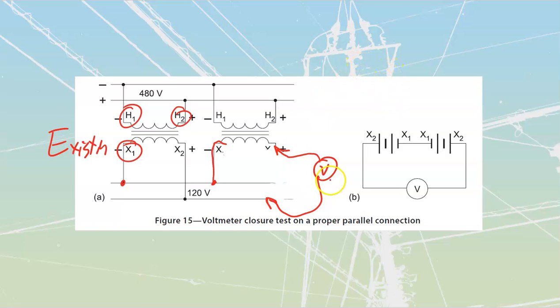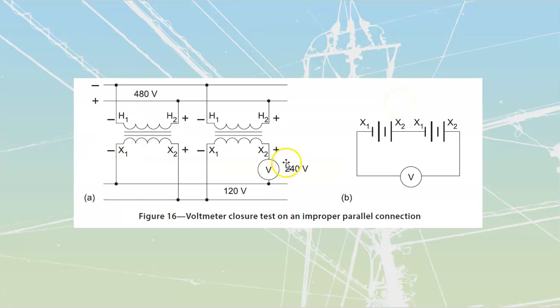Now, there will be small amounts of induction and circulating currents inside of here — it will pick up a little current, inducing a little voltage. So in reality it could be 0 up to maybe half the rated voltage. If this is supposed to be a 120 volt bus, we might see anywhere from 0 to 60 volts or so. That's fine, because that's just what we refer to as magnetizing current. What we don't want to see is the second case.